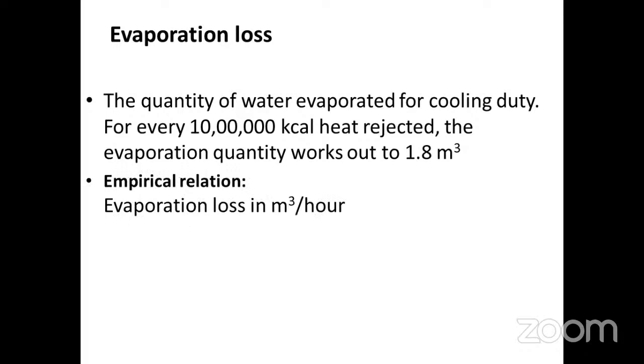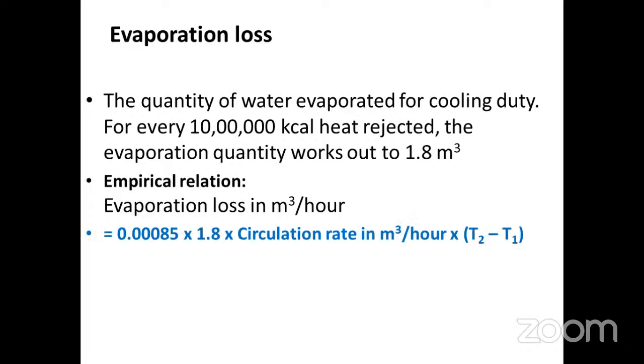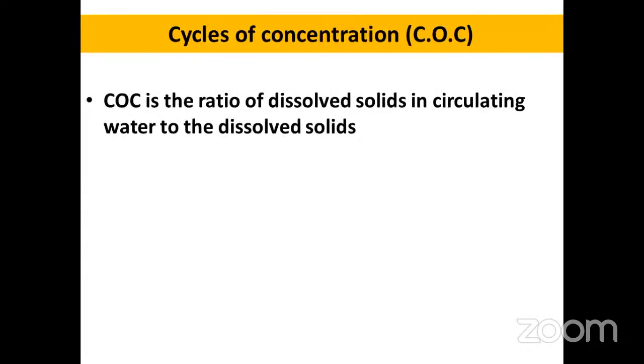There is an empirical equation to calculate this. Evaporation loss in meter cube per hour is equal to 0.00085 into 1.8 into circulation rate in meter cube per hour multiplied by T2 minus T1. Actually, there are very few problems. I'll search for problems in the examination and present them in the next class. Just keep it in mind. COC is the main factor.